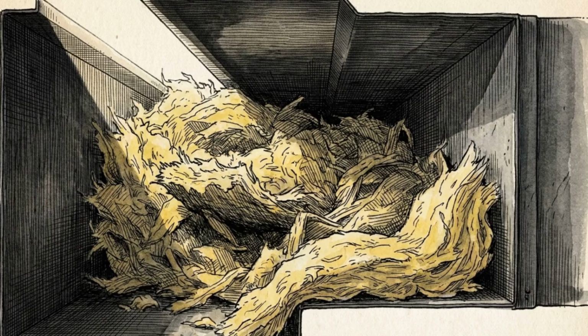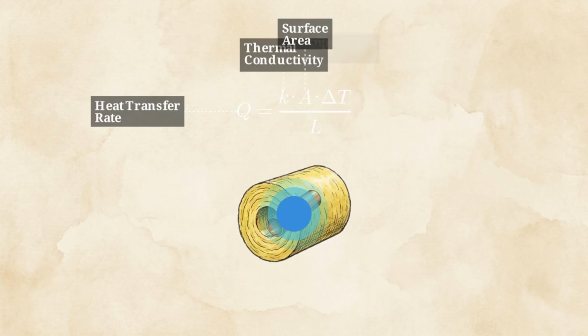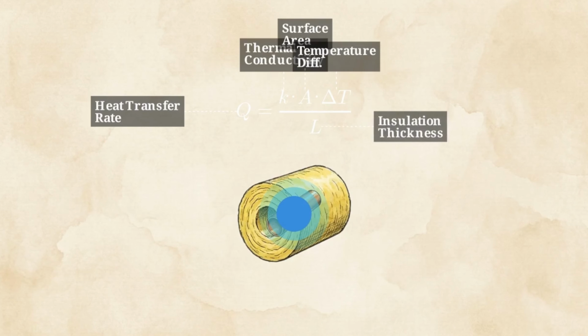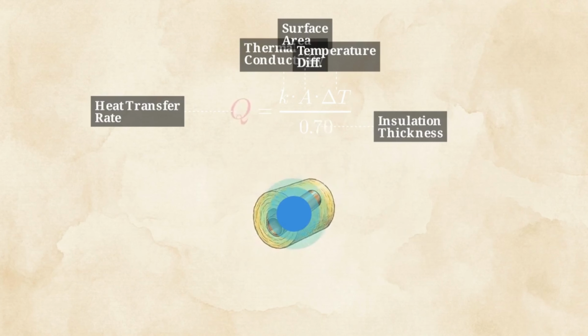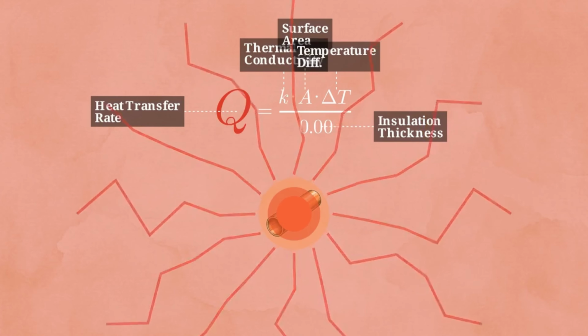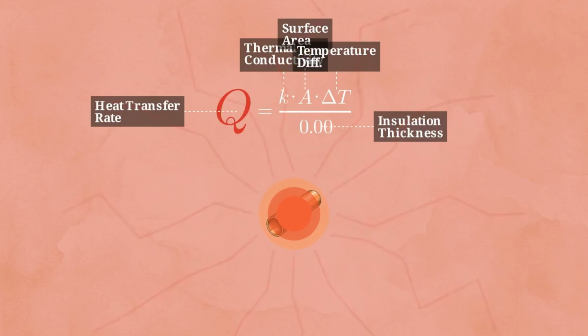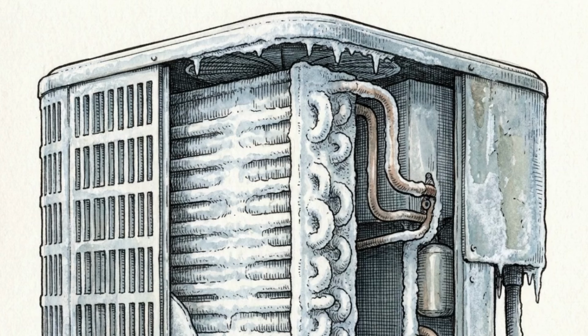They systematically chew through and harvest fiberglass ductboard and pipe insulation to build their nests. This heat flow equation governs an HVAC system's efficiency. Heat transfer, Q, equals thermal conductivity times surface area times temperature difference divided by L, the insulation's thickness. As rodents strip insulation, L drops to 0. This causes Q to massively spike, bleeding heat prematurely. This thermodynamic bleed completely wipes out the benefits of modern high-efficiency SEER ratings.